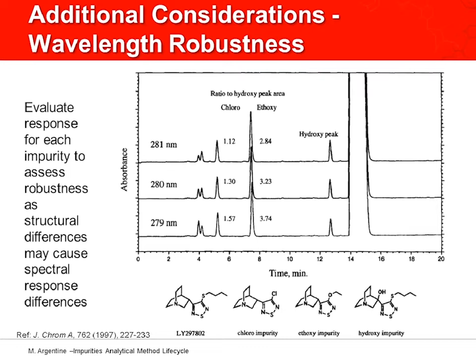Since I mentioned a comment around response factor correction, I thought I'd take a moment just to briefly remind folks that looking at spectral profiles around impurities is important, to make sure that as one is defining the desired detection wavelength, one considers those factors. But there may be instances where wavelength robustness may be an issue based upon even knowledge of that spectral information. In the example shown here, and if you want more information, you can see the J. Chromatography A article on which this is based, impurities that may be even structurally fairly similar to the API may have very different spectral responses. And in this illustration, a 1 nanometer difference in wavelength has a fairly significant impact on results for individual impurities. A 1 nanometer wavelength is typically well within, or tighter than, some of the typical instrument wavelength accuracy qualifications that are routinely performed.